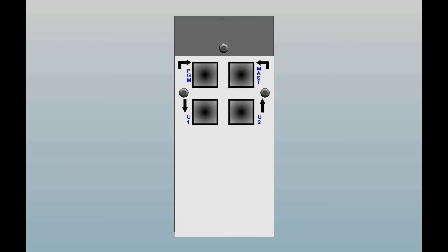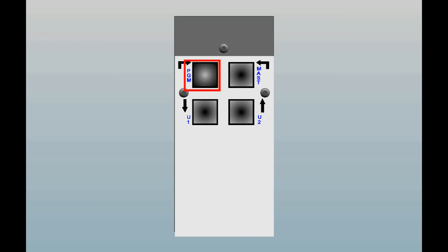There are four square push buttons on the front panel. In the normal measurement mode, the upper left one allows you to enter the program mode of the column. It's necessary to hold the button in for about three seconds in order to enter the program mode. This is done deliberately to avoid accidentally getting into that mode. You can also set up a security code number to prevent unauthorized entry into the programming.